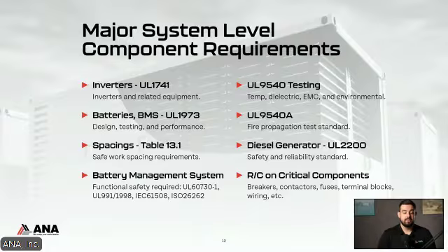The batteries in the BMS must be 1973. So you may have cell level 1973 certification, but if you put that into a module or a battery pack, for example, let's say 40S or 40S2P, it doesn't matter. Once you take that cell and incorporate it into your own battery pack, that new configuration must now be evaluated to 1973. And that BMS that you're using must be evaluated in that configuration as well. So, something to think about. You may think you're in the clear with 1973 cell level certification, but that's not always the case.